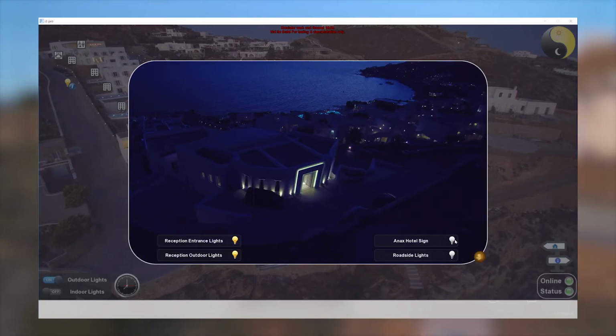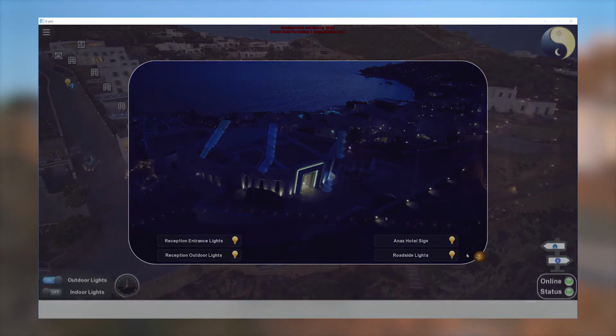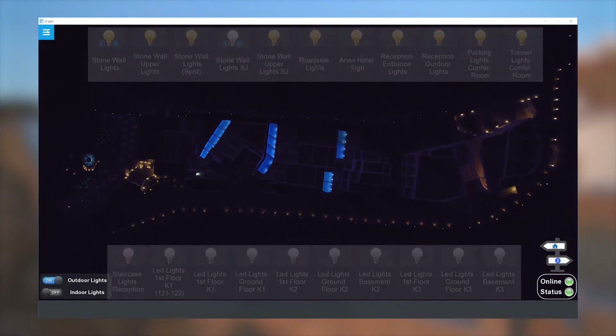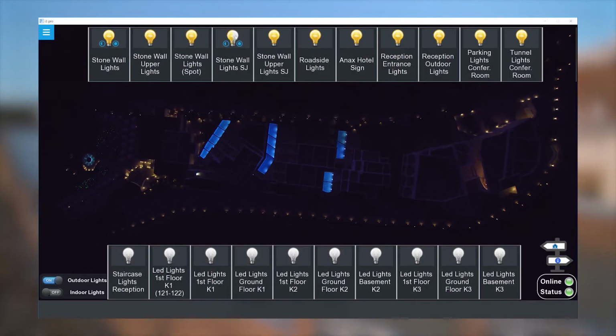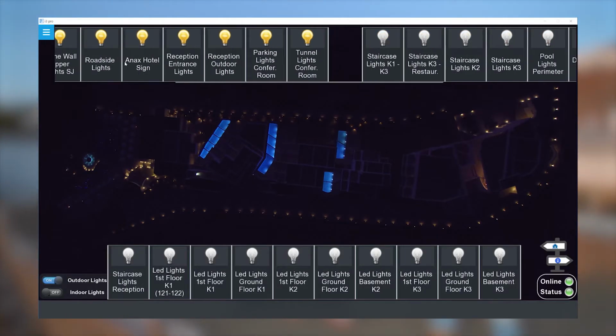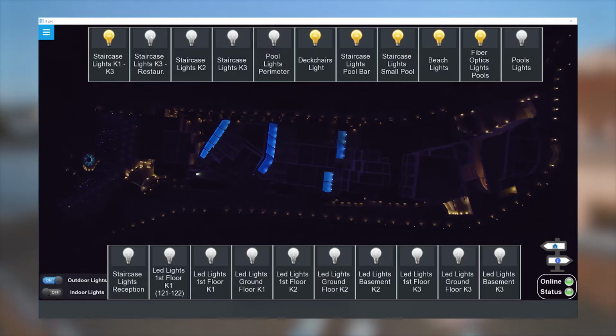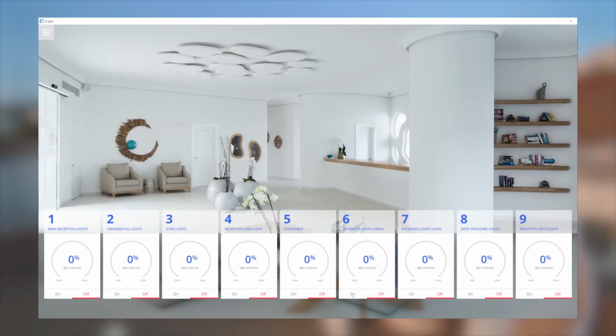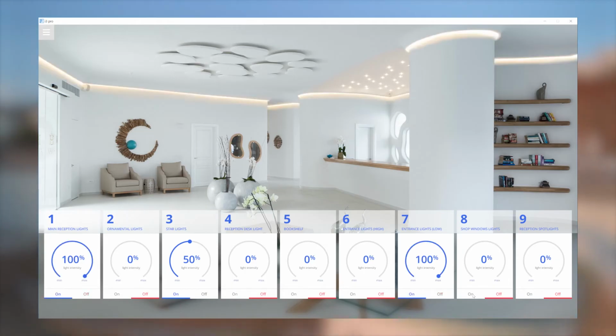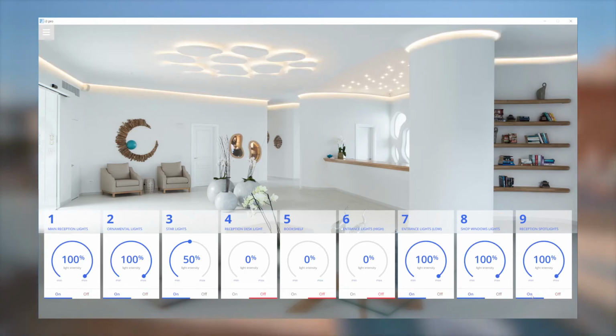KNX is a worldwide standard for home and building control. In contrast to a standard electric installation, there is no hard-wired connection between the control units and the power supply. For example, a light switch is not directly connected with the respective light. Instead, devices and electric assets are connected via the bus, which runs on 29 volts.